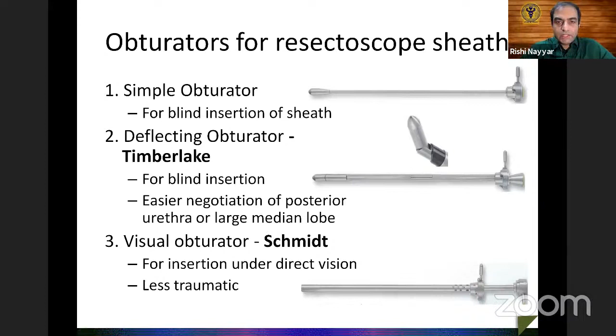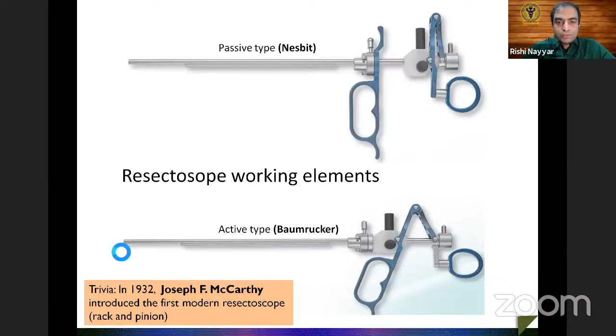The working elements, we all know that there are two types, active type and the passive type. Passive type means that the working handle remains backward, which means that when the electrode is attached to this handle, it would remain inside the cavity of the resectoscope sheath in its resting state. Whereas in the active type of working element, the electrode keeps protruding out of the resectoscope sheath in its resting phase, and it has to be actively pulled back all the time so that it resides inside the resectoscope sheath without injuring the urethra.